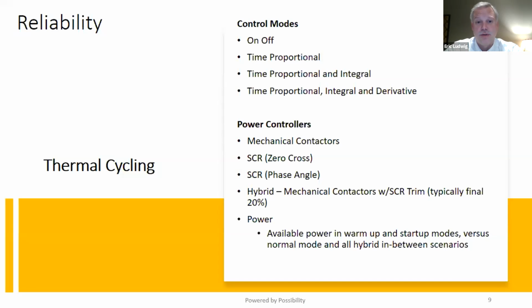Let's talk a little bit about reliability and thermal cycling. These big electric heaters have steps or circuits in them that represent a bundle of heating elements, and they need to be switched on and off somehow. There are a couple of main technologies used in the market to switch these large resistive heating branch circuits on and off, and there are different control modes associated with that. You've got your typical on-off—I'm just going to turn it on sometimes and off sometimes on a regular interval. And then you have time proportional, and time proportional-integral-derivative, also known as PID. These are the different types of control modes usually embedded in a process controller that can be used to control the temperature at the outlet of that particular heater.